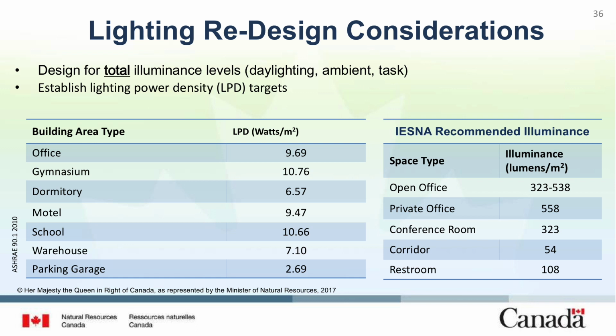For example, in an open office with a recommended illuminance of 323 to 538 lumens per square meter, it's better to hit an illuminance target closer to 323 lumens per square meter and to reach that target with a combination of overhead and task lighting. It's the same for lighting power density. We have listed here a lighting power density of 9.7 watts per square meter for offices. There's no reason that you can't hit a target of 6 to 7 watts per square meter within these facilities. With some of the new lighting technologies, you can see designs even below 5 watts per square meter. So there's opportunities to drastically reduce energy usage.